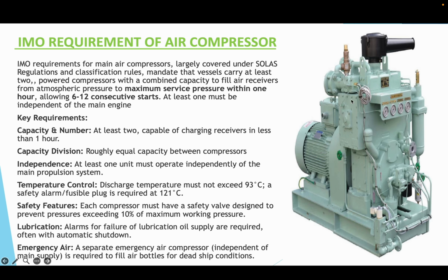So it means that if there are 2 air compressors, each air compressor will be able to fill the air bottle up to maximum service pressure that will be able to give 12 consecutive starts. It means that each one is redundant to the other.